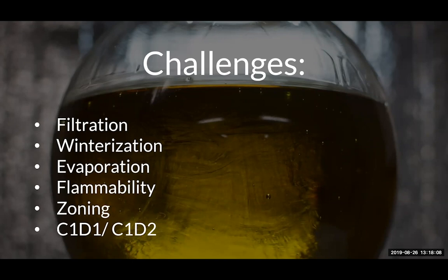The other reason we have these separate is the C1D1 and C1D2. A lot of people think those are the exact same thing as control areas, which we discussed in flammability, but they're actually not - they're separate. One's from the electrical code, one's from the International Fire Code. The C1D1 is electrical code, and that's literally just very linear - the electrical code is pretty basic. It states that if it's open to the process at any point in time to the environment, it's a C1D1. If it's closed to the process, it's C1D2. That's literally all that means. There's a lot of misconceptions about how that works, but the electrical boundaries generated by those devices cascade into the equipment around them - that's where a lot of people get caught up in the challenges.